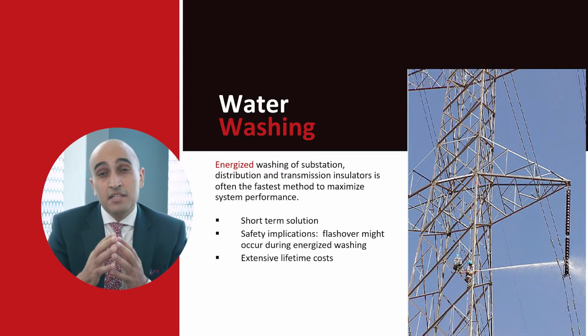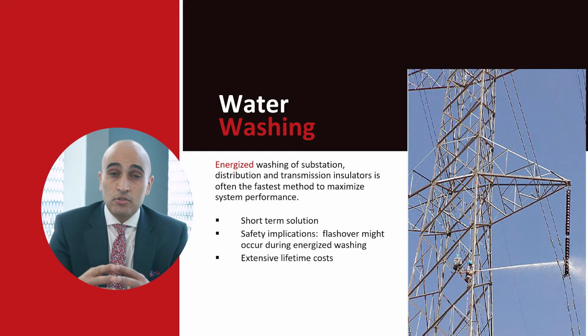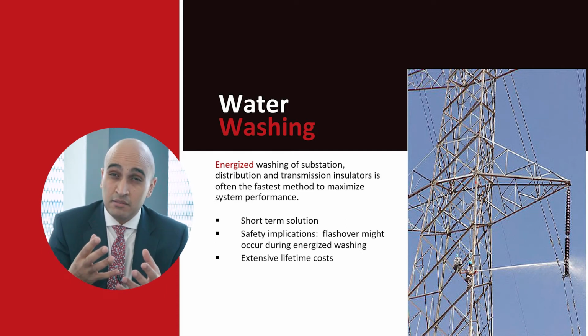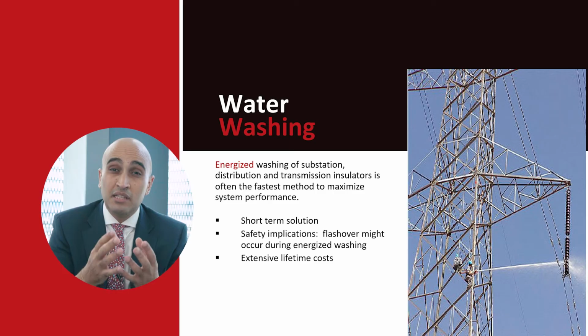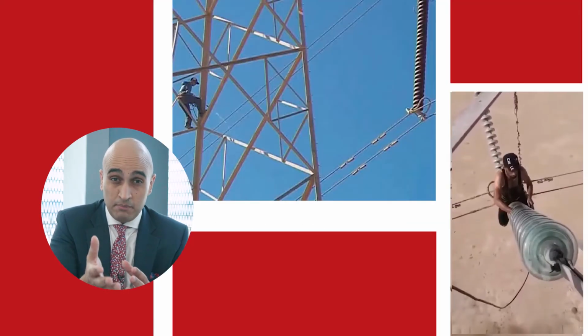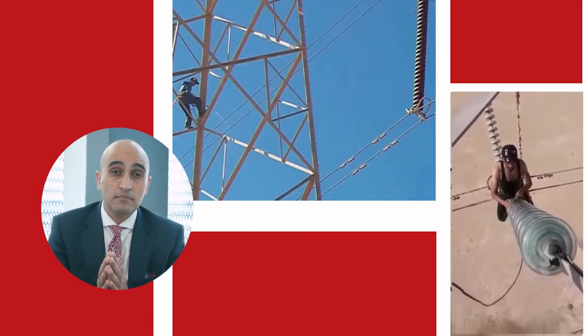So the first approach is cleaning the insulators. Cleaning the insulators could be done using a simple rag, or by washing the insulators in live line condition or in cold condition using high pressured water. This is a short-term solution because as soon as we clean the insulator, if the source of the contamination is still producing contaminants, the insulators will still be contaminated. And also there is some serious safety implication to cleaning or washing those insulators. For example, in the video you are going to see right now.